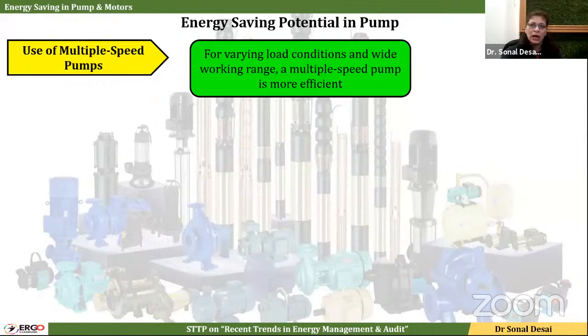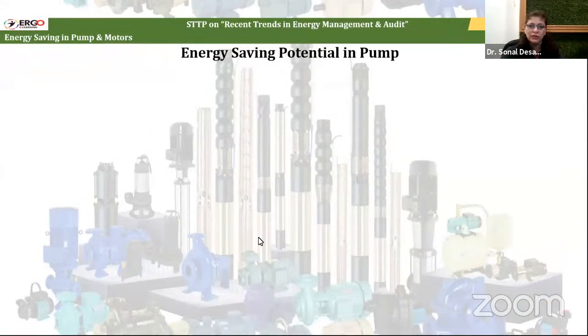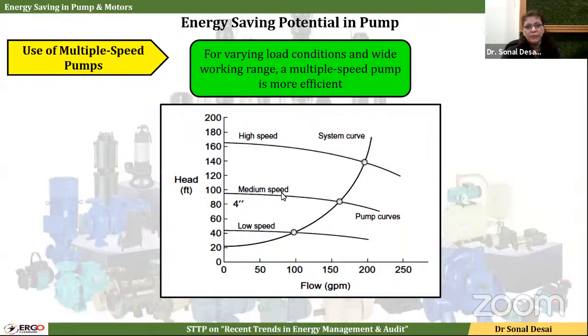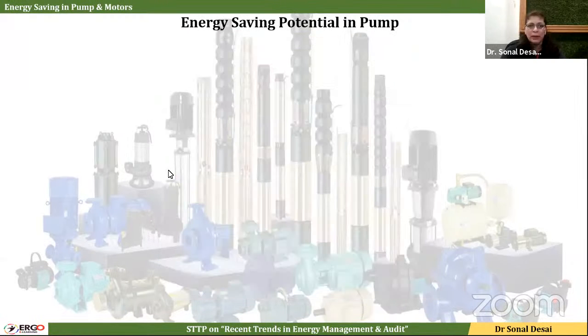Go for a multiple speed pump. A high speed, low speed pump is there. A very good example of that flow chart is given. When you're operating at high speed, its performance point is this. On the same system curve, when you're operating at a lower speed, it is at this point, and at the lowest speed, it is this point. So rather than controlling the flow by throttling, which will shift these points to this side, make the head increase and ultimately increase power consumption, it's always good to reduce the speed of the pump.